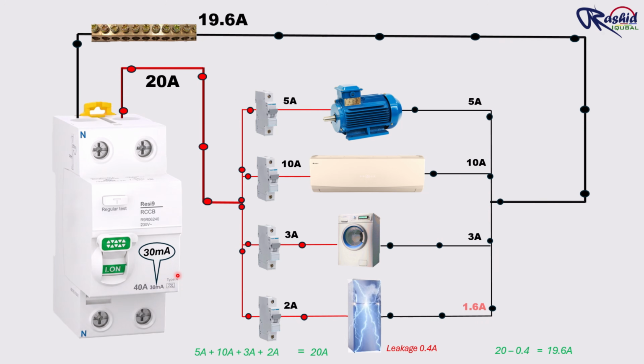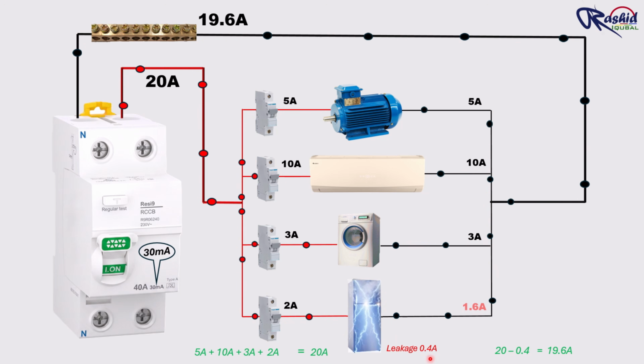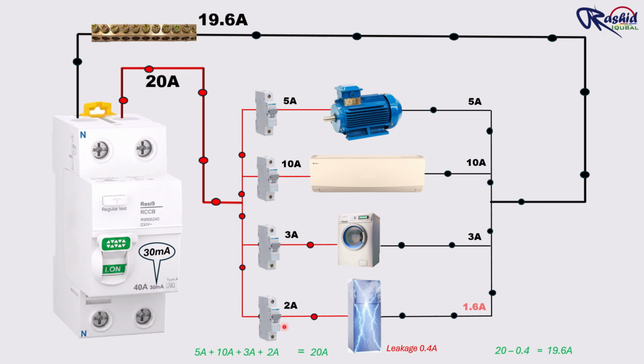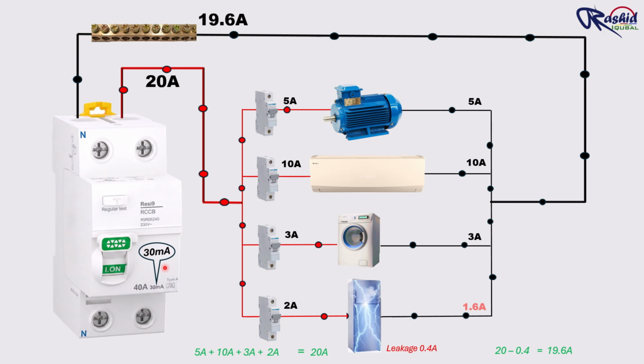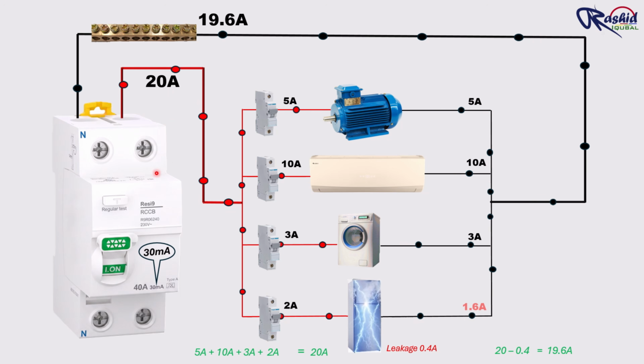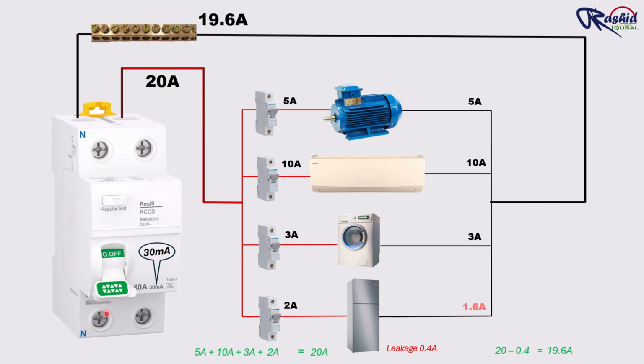But in our example, the leakage current is 0.4 ampere, which is much higher than the RCCB limit. So when the RCCB detects this difference between phase and neutral current, it trips within milliseconds and disconnects the power supply, helping to protect people from electric shock.